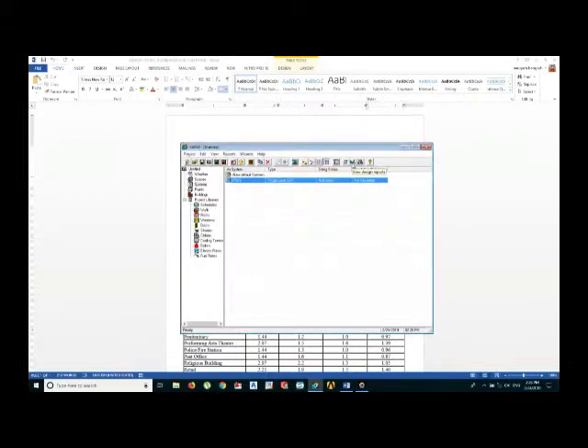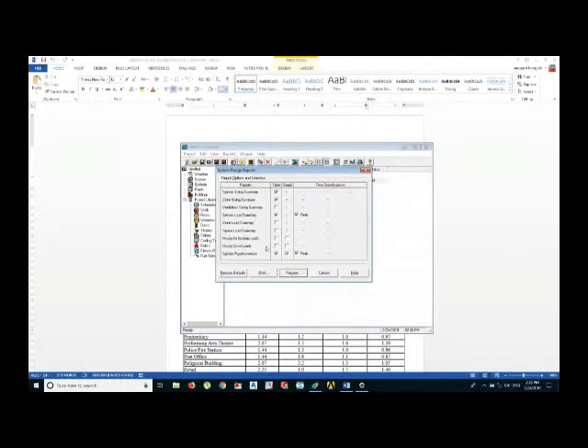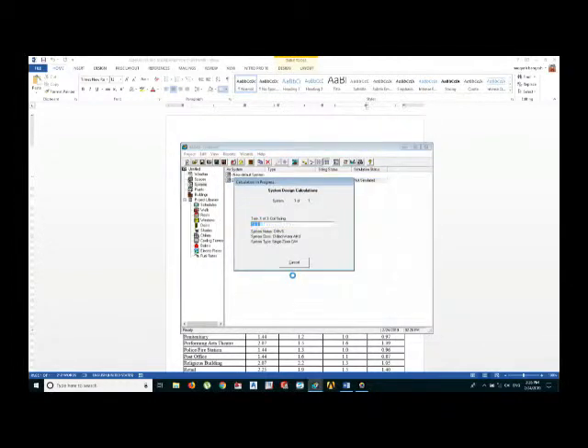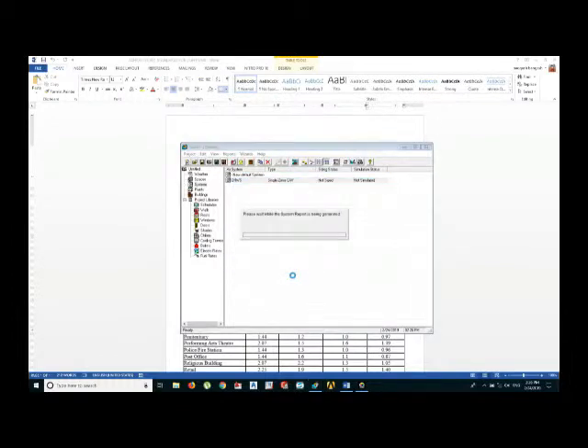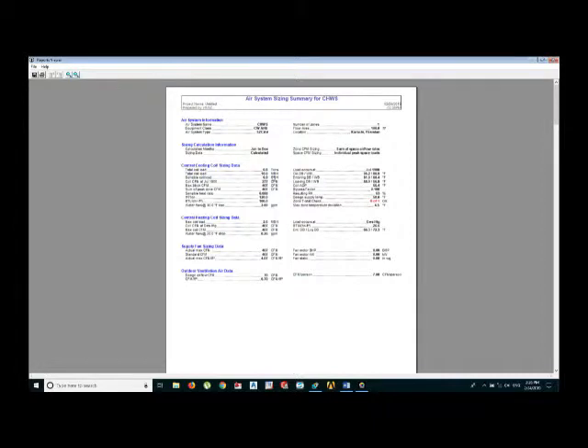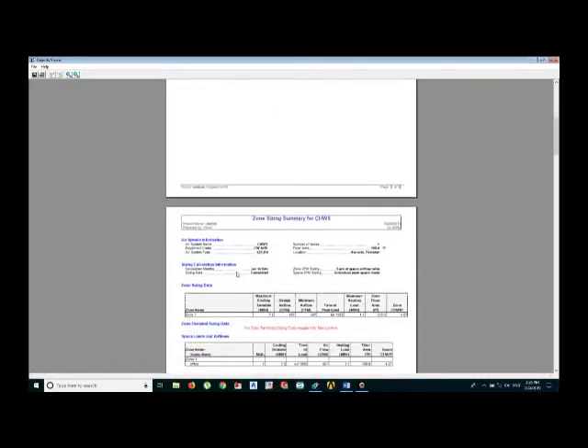And after this, press this 'New Design Report' and select the parameters you need: zone sizing, assembly, ventilation - check these if you need these. If you don't, just press preview. So this is the load of your system. Total coil load is 0.8 ton, which is 10 kBTU. This is the CFM: 277 CFM. And these are all the data you need for your system.